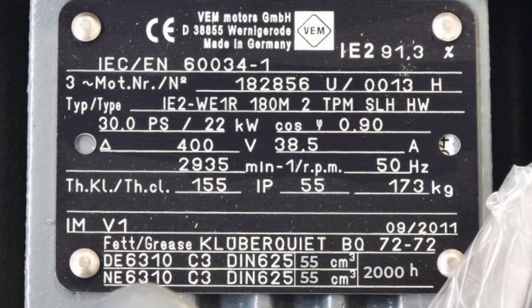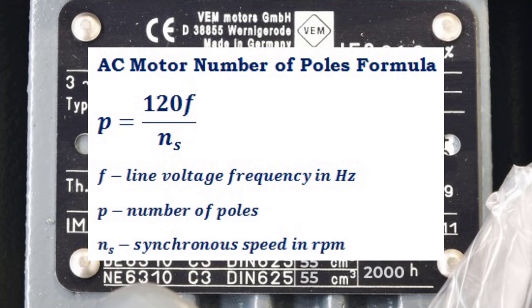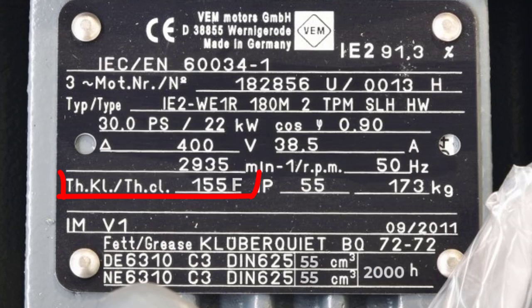The rotor speed is 2935 RPM, which is near the synchronous speed of 3000 RPM. We can deduce the number of poles using the equation: P = 120 × frequency / synchronous speed. So P = 120 × 50 Hz / 3000 RPM, which equals 2 poles.